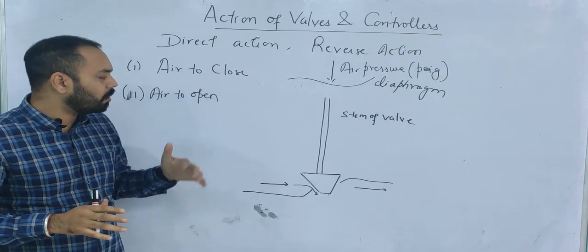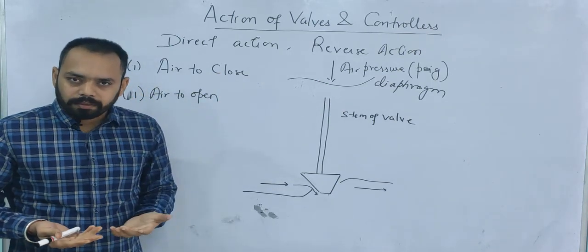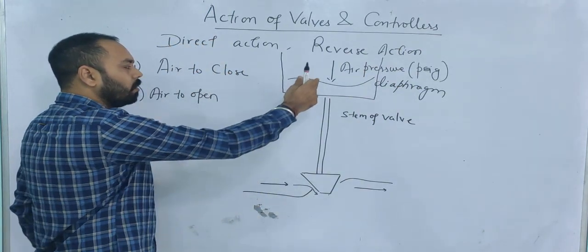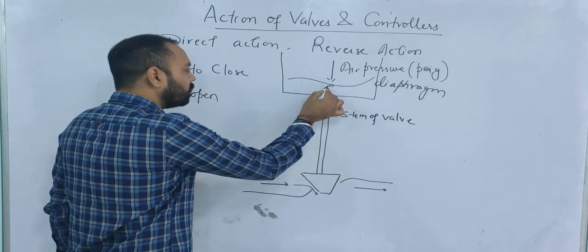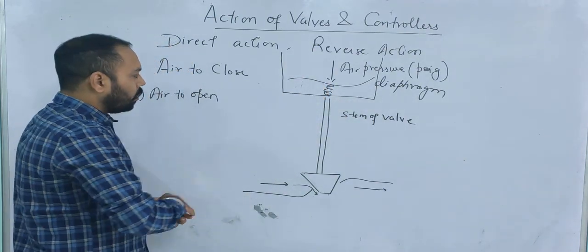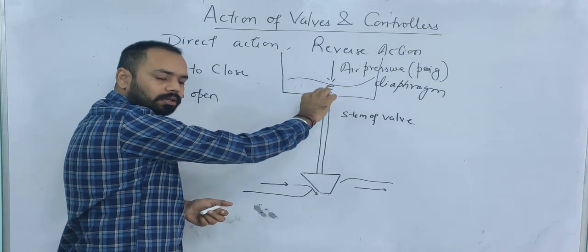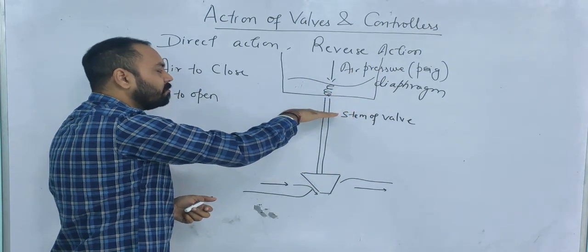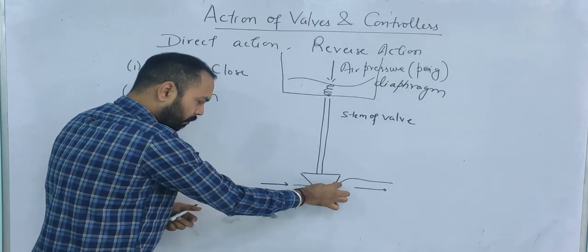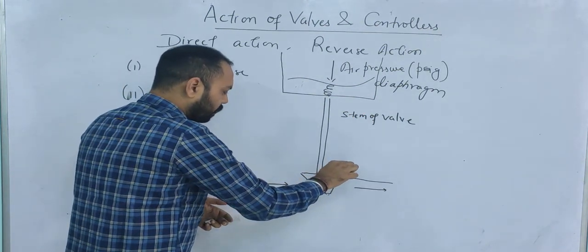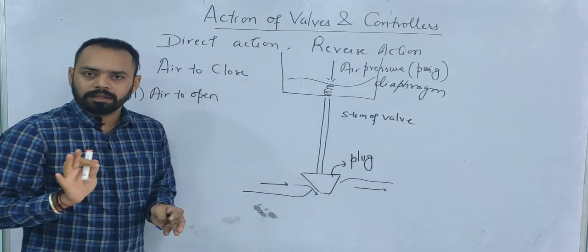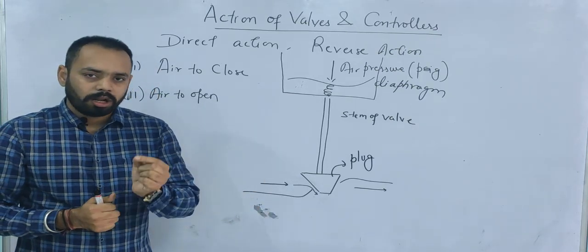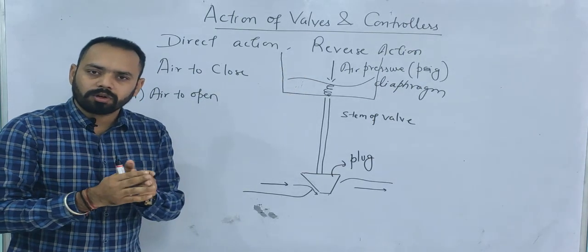Whether a valve acts as air-to-close or air-to-open depends on the position of the spring. Suppose the air pressure is applied from the top and the spring is present below. As the air pressure increases, the spring gets compressed and the valve will be closed. If the air pressure is at its maximum value, the stem moves maximally downward and the gap is completely filled with the plug — resulting in zero flow through the valve.